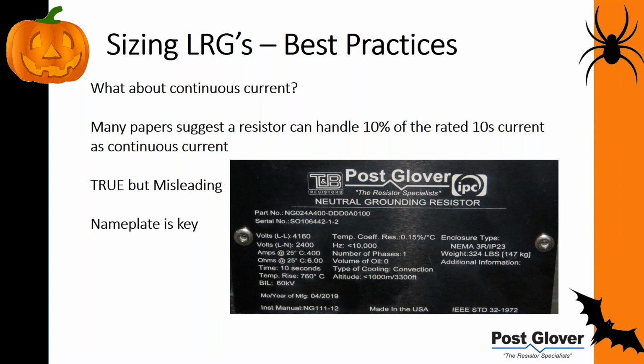What about continuous current, like I just said? Well, I've read a few papers, and maybe some of you have read as well, that a resistor can handle 10% of the rated 10-second current. If you didn't know, the most common rating for neutral low resistance ground systems is 10 seconds, which comes with the IEEE requirement of a 760 C rise or less. You can kind of see that if you have good enough eyes. I know it's probably small on your screen. I have a big old screen, so I can see it pretty easily. 760 C here. So the point is that I'm not going to dispute that. I think it might be true, generally speaking.